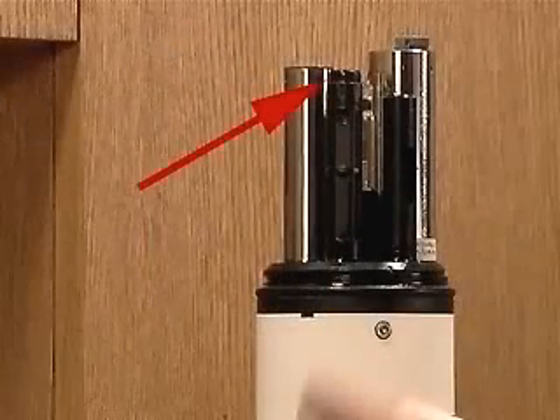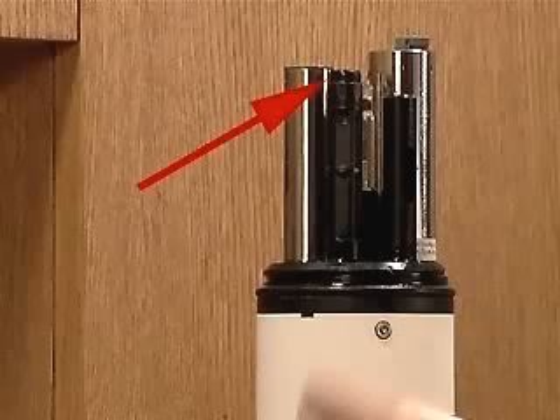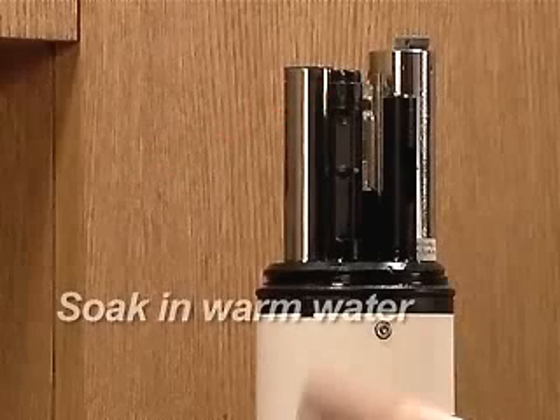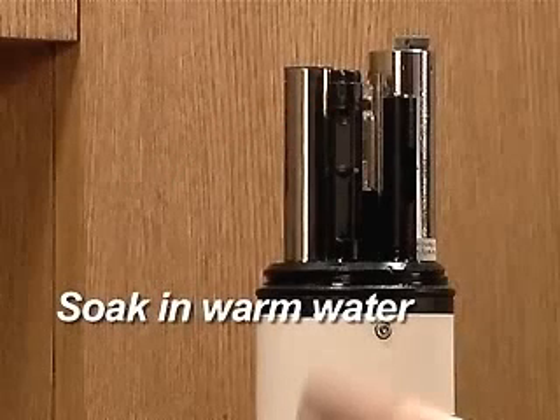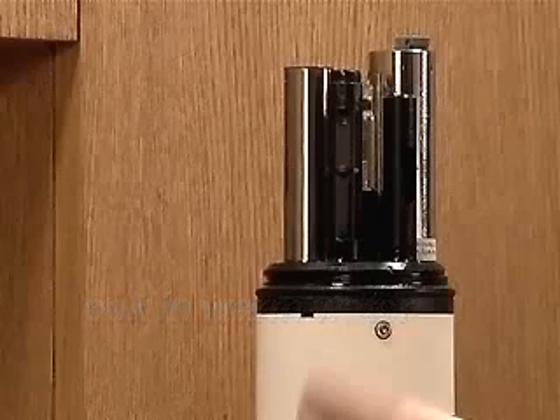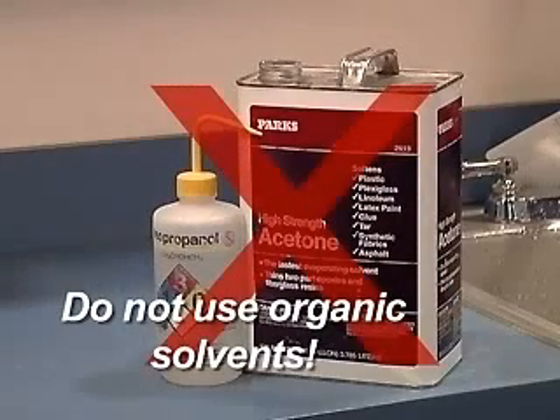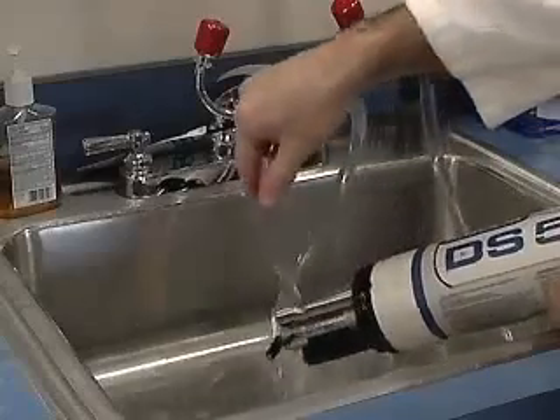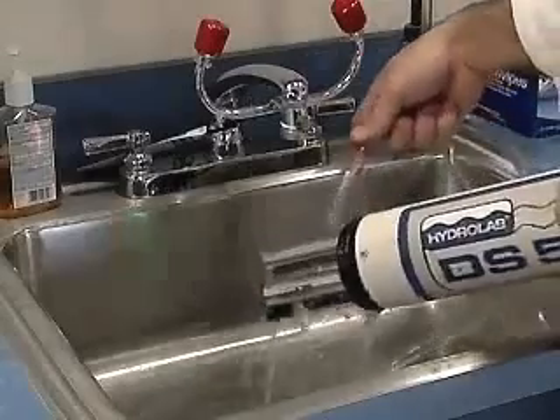Hard scrubbing will remove the black coating from the outside of the sensor cap. If more than half of the coating is removed, the cap must be replaced. If deposits on the sensor are difficult to remove, soak the sensor in warm, fresh water until the deposits soften. Never use organic solvents such as acetone or methanol on any part of the sensor or cap. When the sensors are clean, the LDO is ready to calibrate.